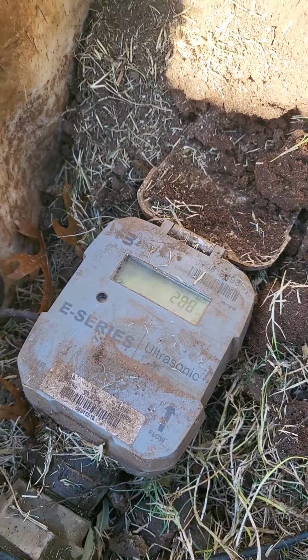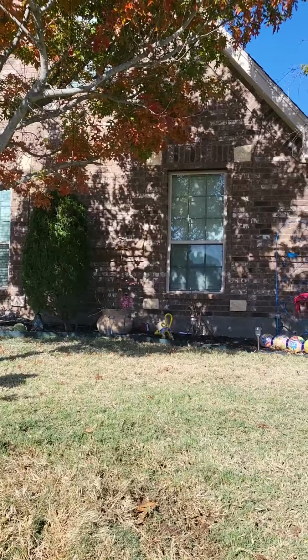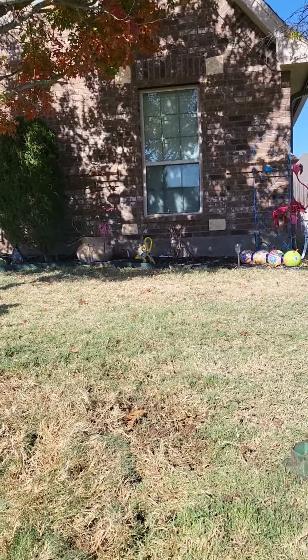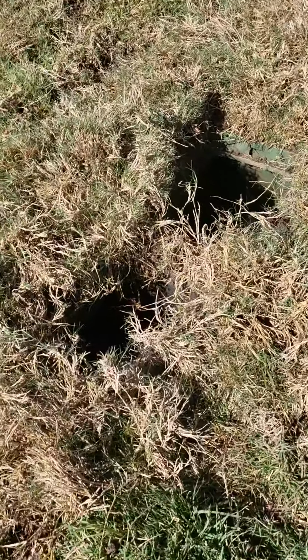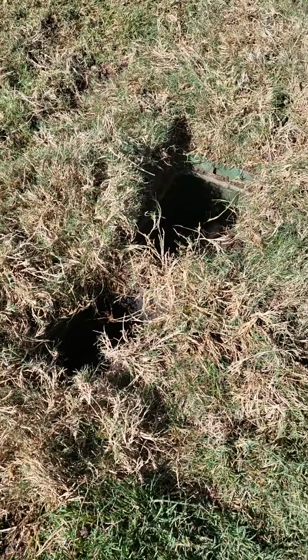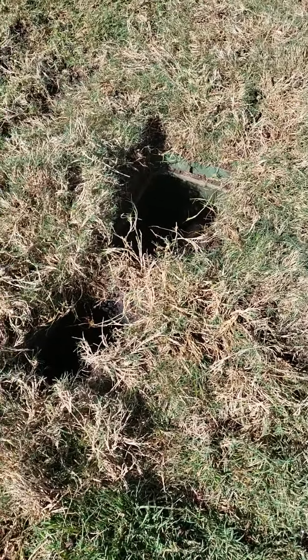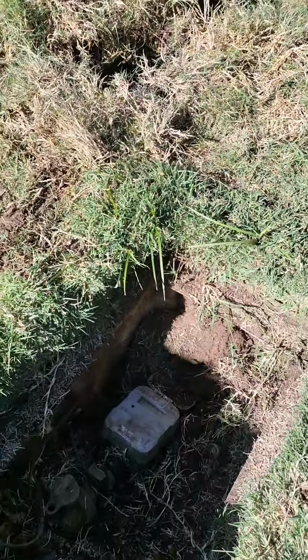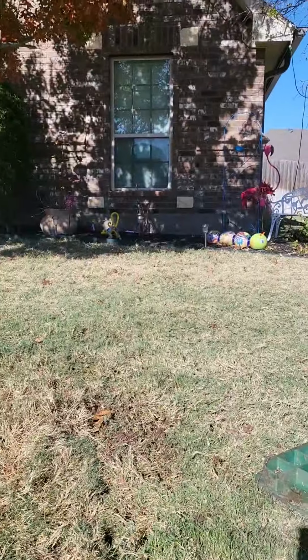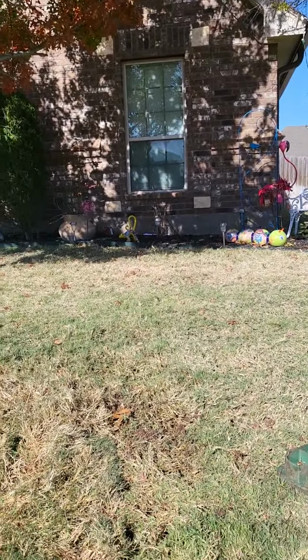Now what we've got to figure out is whether the leak is coming from the house or from the sprinkler system. The first thing you want to do is go to your isolation valve. You're going to have two boxes right next to one another, and they should be within 5 feet of the water meter, or somewhere up by the house near the customer shutoff valve.